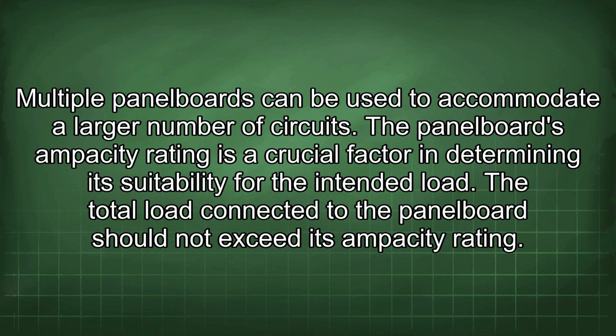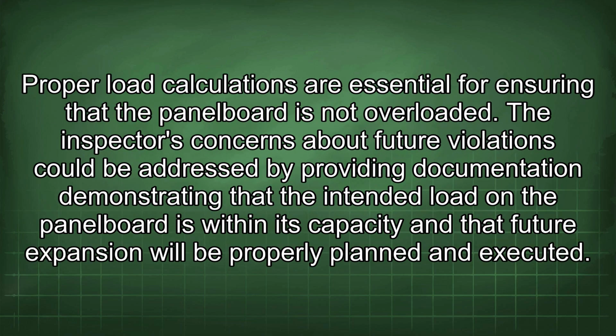The total load connected to the panel board should not exceed its ampacity rating. Proper load calculations are essential for ensuring that the panel board is not overloaded. The inspector's concerns about future violations could be addressed by providing documentation demonstrating that the intended load on the panel board is within its capacity and that future expansion will be properly planned and executed.